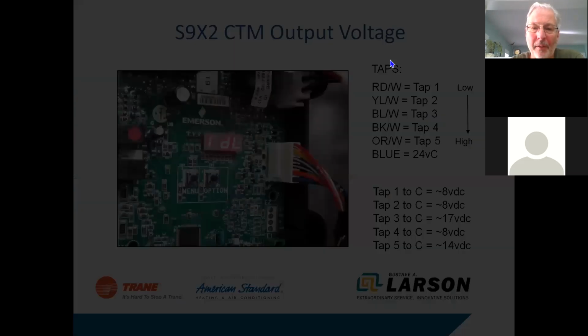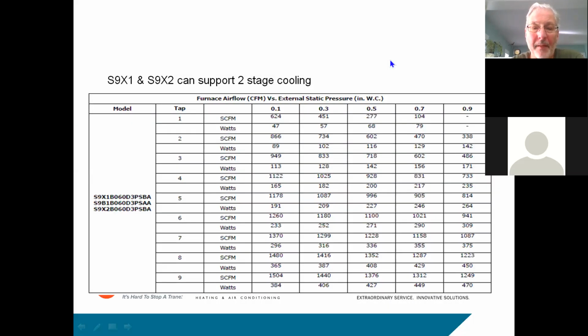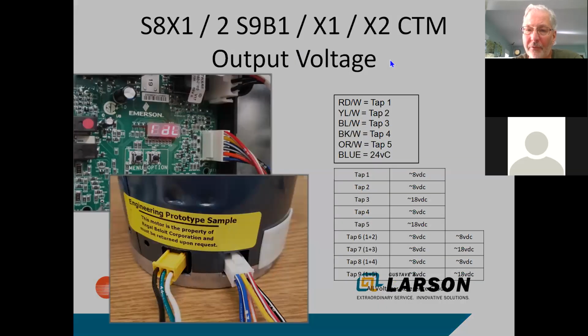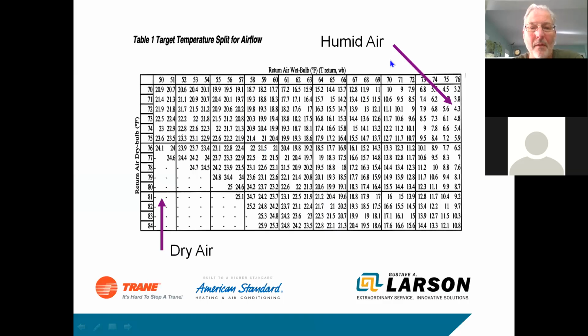But backing up just a little bit, this is probably key. If you got a 3-ton system and you got a 0.5 static, you want to set that cooling tap on tap number 7, okay? If you have a 0.9 static, you've got to be up on tap number 8. So if you know your static, you can set up your airflow pretty easily on these furnaces. Now, if you don't want to do that, you can always do the old way of just hit and miss.